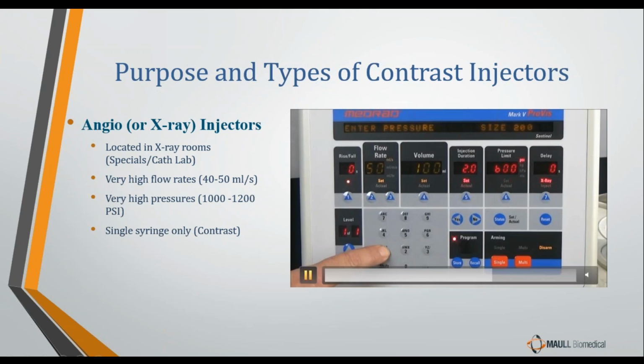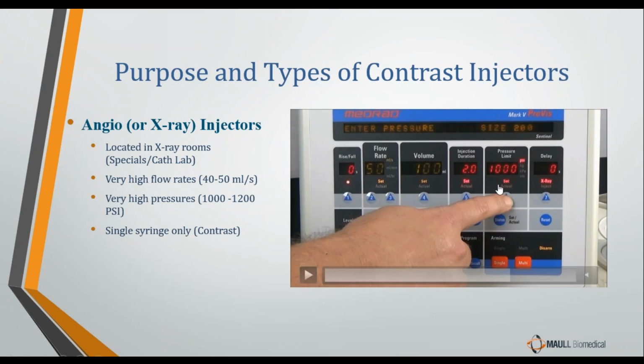Back up a little bit here. Angio injectors are also capable of very high pressures. Now that is pressure limit, and you'll notice that is in PSI. That is 1,000 pounds per square inch. In some instances, these injectors can be programmed to go as high as 1,200 PSI.